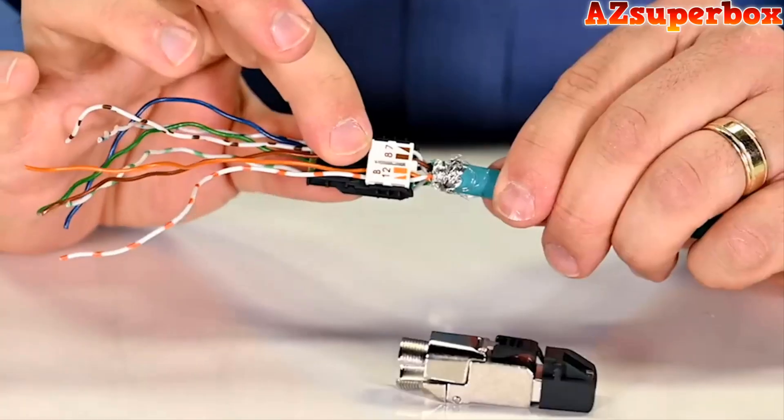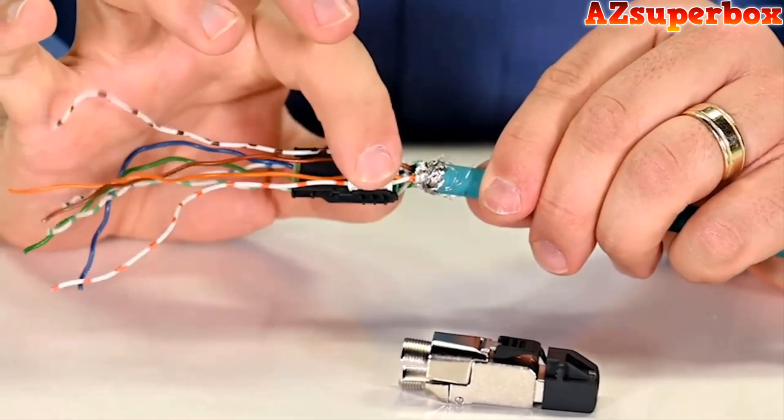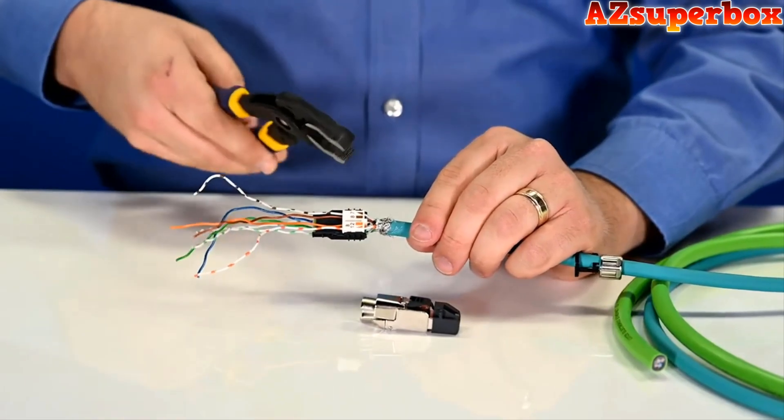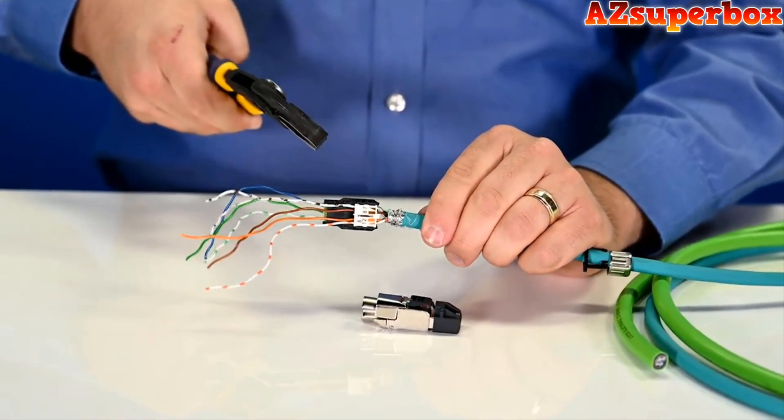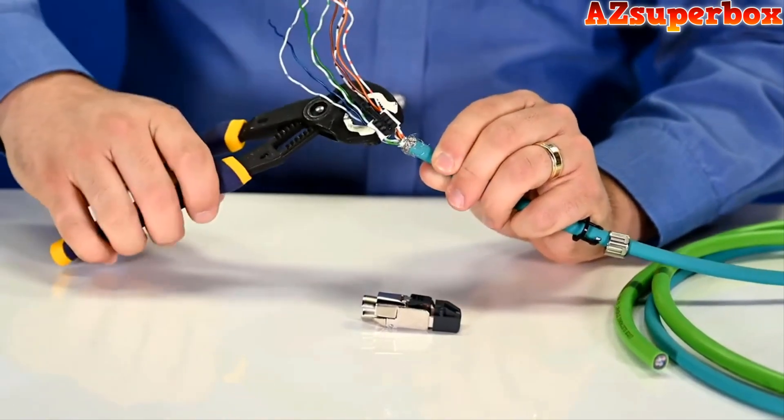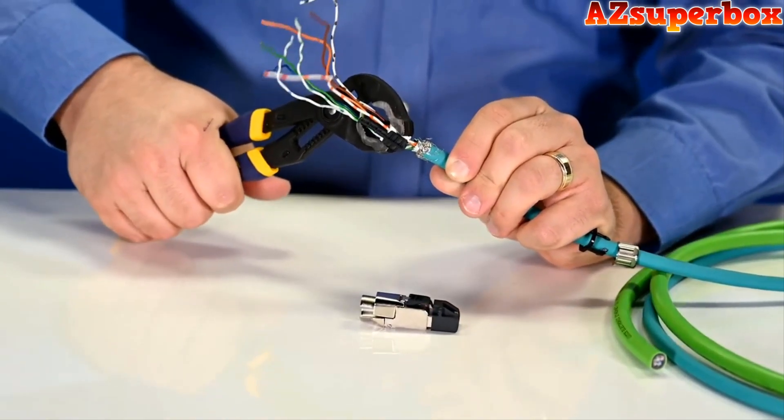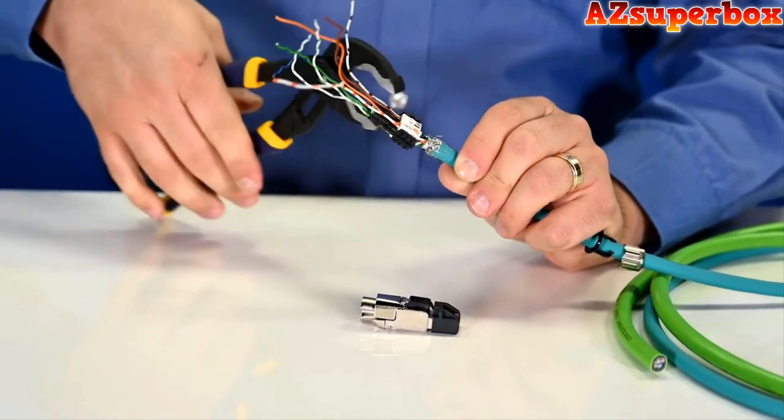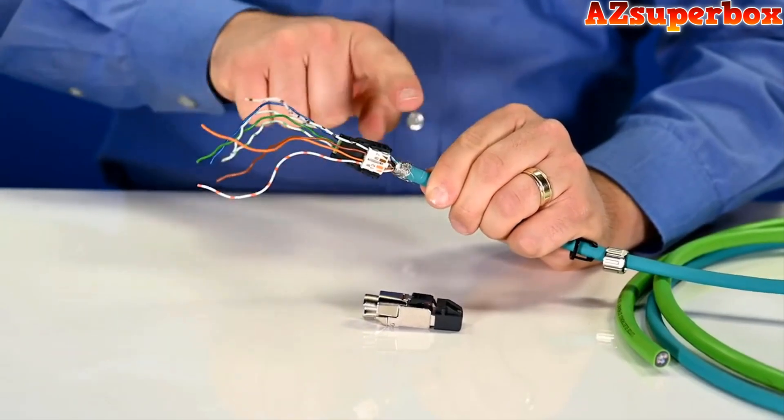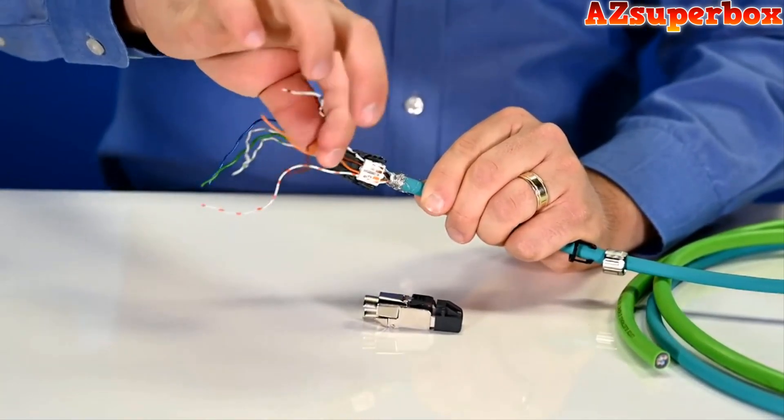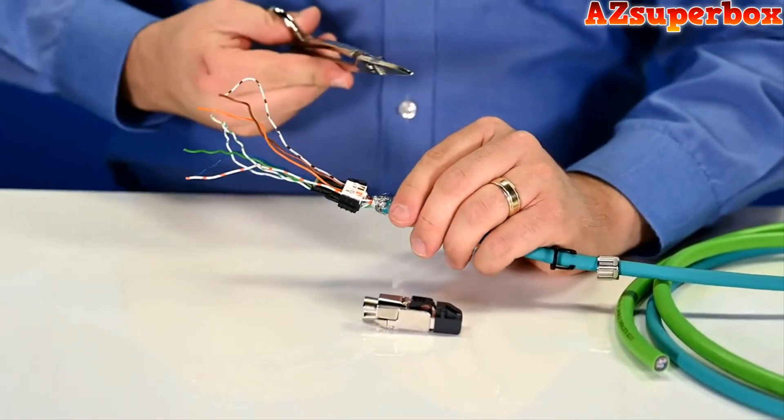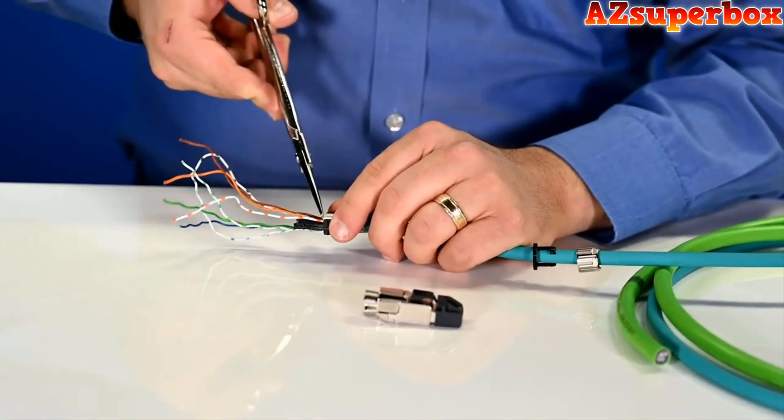Now that we have that nice and tight, it's time to engage those contacts that we talked about. And all you need to do this is a pair of channel locks or something else that applies parallel clamping force. So we want something that's going to put pressure on either side of that connector. And we simply clamp straight down. Make a nice firm connection. And you see that also loosens up this protective plastic housing. Next step is to get rid of all this extra conductor that we have here. So just take a sharp pair of scissors or a pair of snips and we can cut that right away.